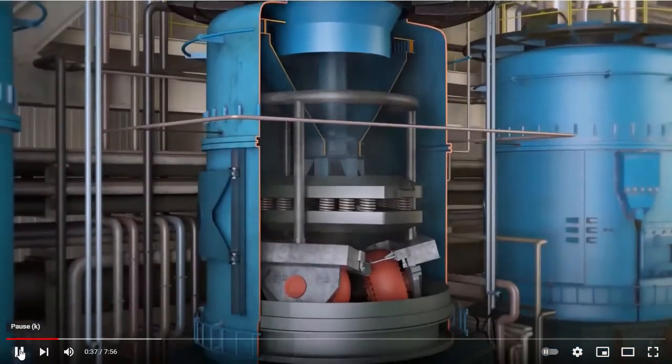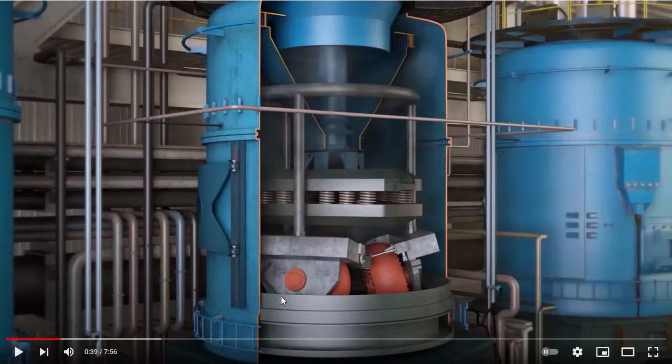These coal mills, you can kind of see how it's spinning down there. It's got these big rollers, just think of them like wheels. That coal comes down into the middle, and then this bed is rotating around, so that coal gets flung out, and then those wheels crush it up into fine baby powder. It's fine enough that we have a big fan that pushes air through here, so it picks up that baby powder and shoots it back up into the boiler, and that's where we get the flame from. That'll get shown here in just a sec. So there's your coal going back up.